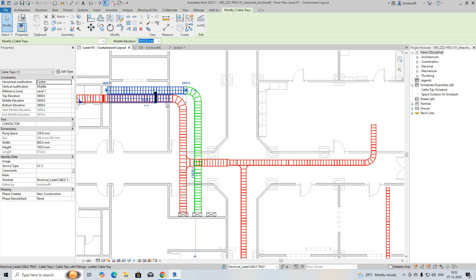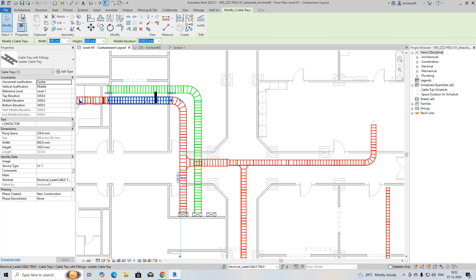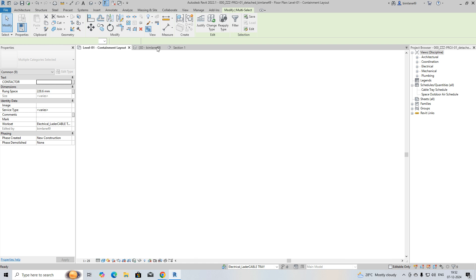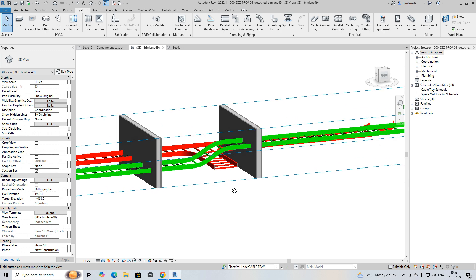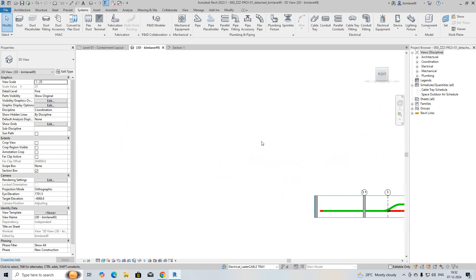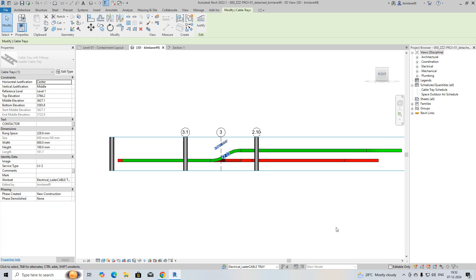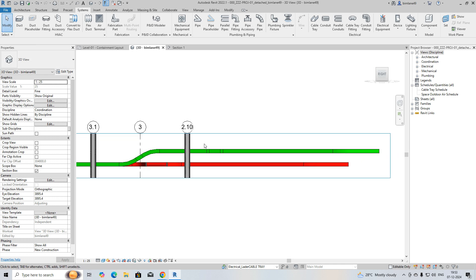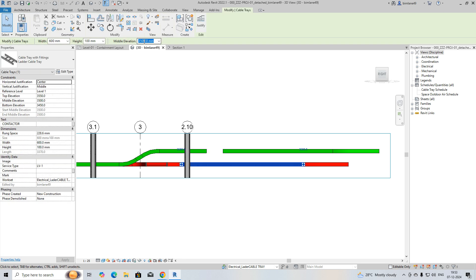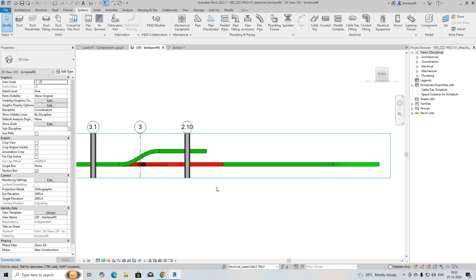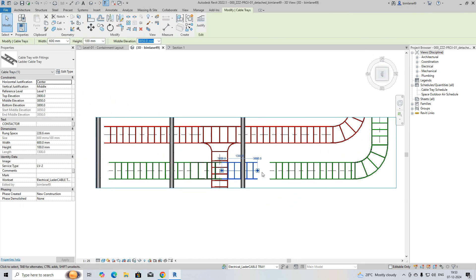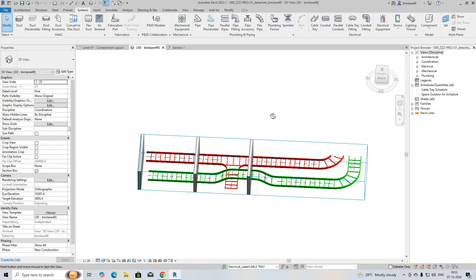In the 3D view, put at least 100mm spacing between them so you can see how the other cable tray is going. Once you need them at the same height after a point, use the Split command (SL) to split this one, remove the section, and copy the middle elevation. Paste that elevation so both cable ladders end up at the same level. You can do the connection in 3D itself and see how the bending works.